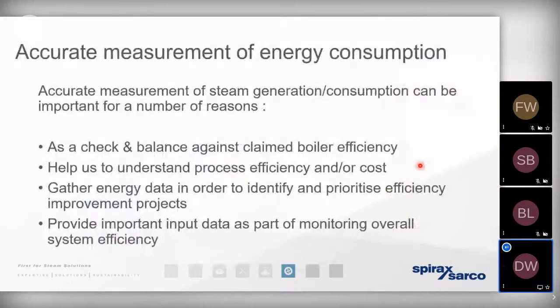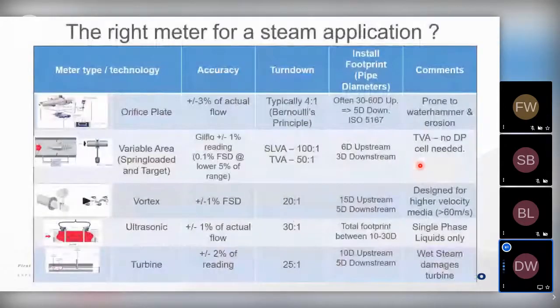Other things that we need to think about is the measurement of the amount of steam that is being distributed and condensed. And just as there's no such thing as a universal steam trap, there really is no such thing as a universal steam meter. There are different types of steam meter that we may want to give consideration to for different applications. But the important things to look out for whenever we're sizing or selecting a steam meter are, first of all, the turn down, and that's the difference between the highest and the lowest flow rates that it'd ever need to read. The next thing is the accuracy, and that's the ability of the meter to read a true and correct value. And then we've also got the repeatability. The repeatability is interesting because that's the ability of the meter to read the same reading time and time again. It might not necessarily be an accurate reading, but it's the same reading.